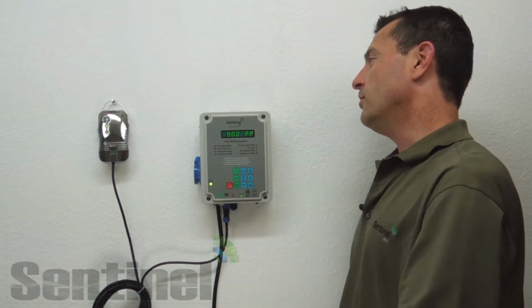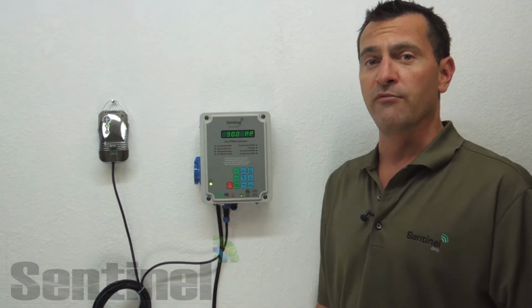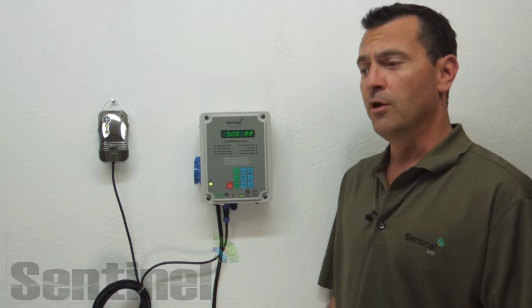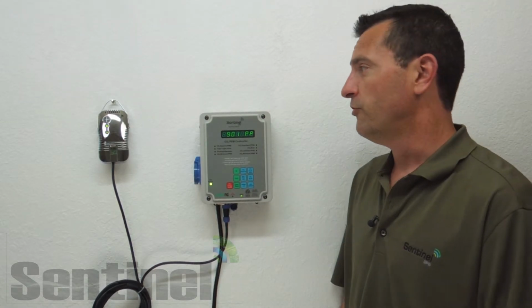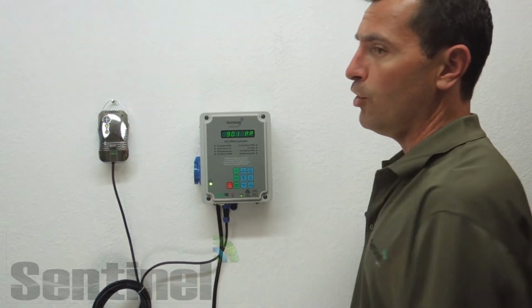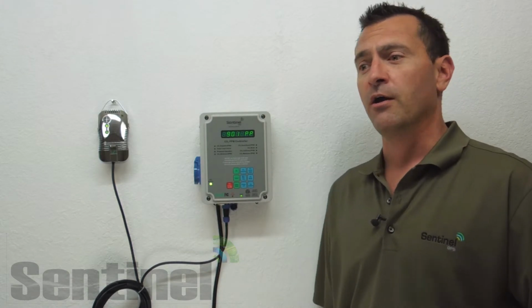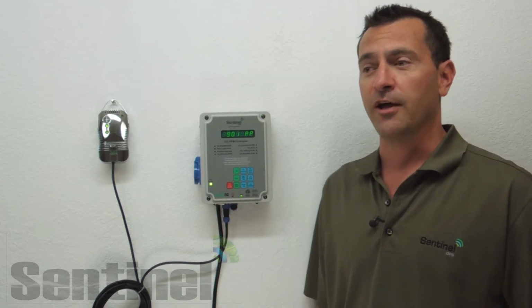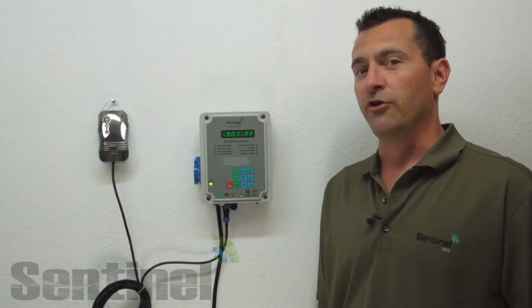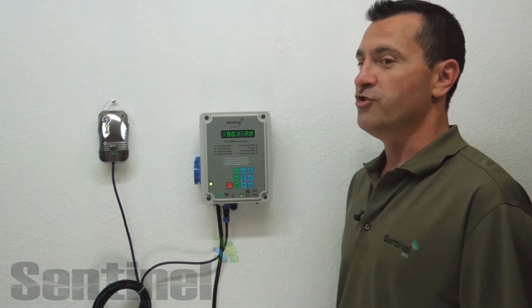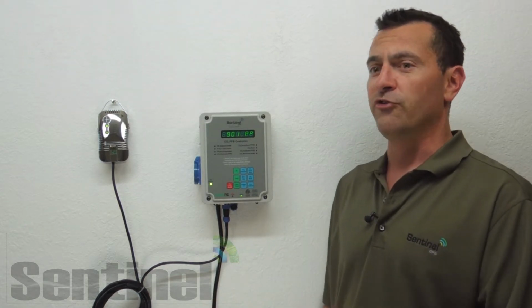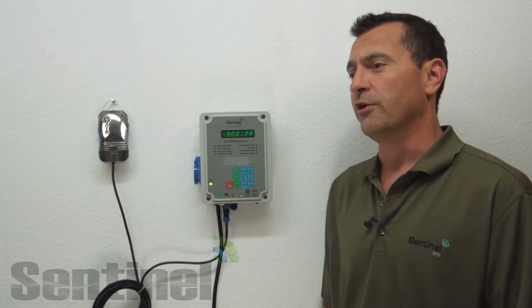Using the CO2 calibrate feature, you can calibrate the unit within your own home. You don't need a reference gas or anything, unlike some more complicated CO2 units. What you do is you take the remote probe and put it outside in fresh air. Make sure to keep it out of direct sunlight. Let the unit run for an hour or so. That allows everything to get to the same temperature. It allows the CO2 sensor to stabilize, gives you a good baseline reading.